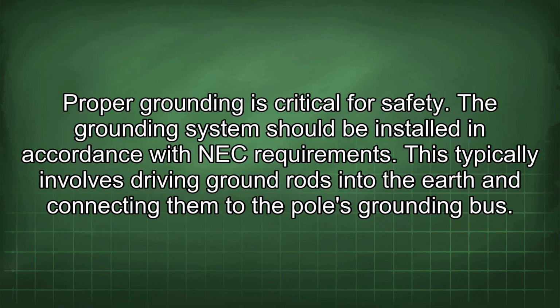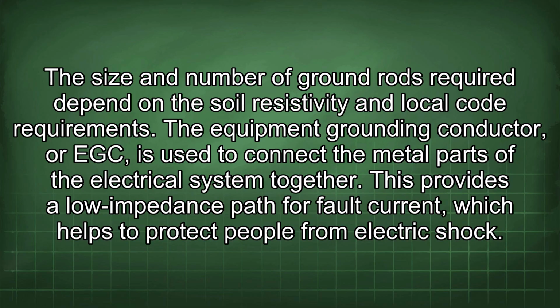Proper grounding is critical for safety. The grounding system should be installed in accordance with NEC requirements. This typically involves driving ground rods into the earth and connecting them to the pole's grounding bus. The size and number of ground rods required depend on the soil resistivity and local code requirements.